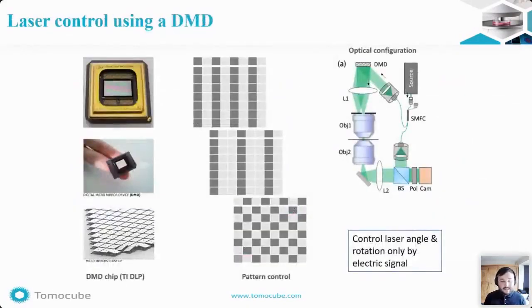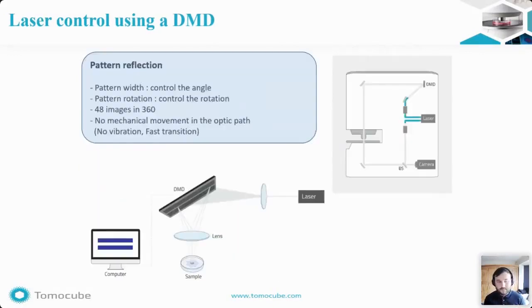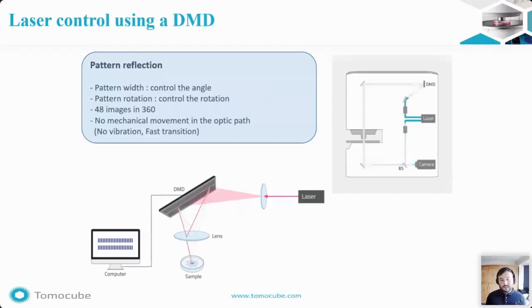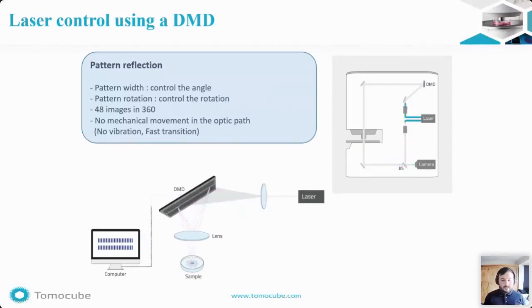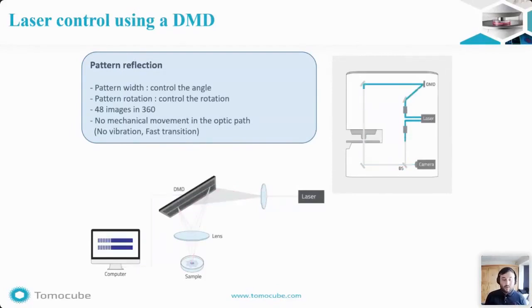This is done using a technology patented by TomoCube called the digital micromirror device, or DMD. This allows the microscope to produce CT-like images by controlling the laser angle and rotation. The DMD allows us to cover 360 degrees by taking 48 images with no mechanical movement. The absence of moving parts allows for fast imaging with high resolution.